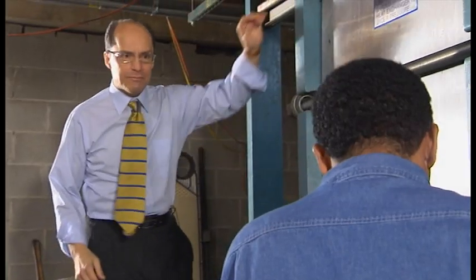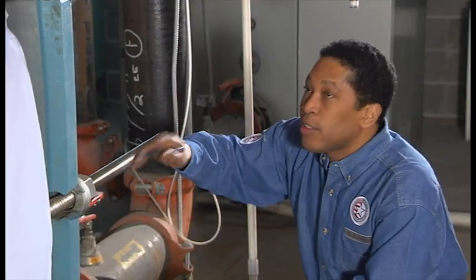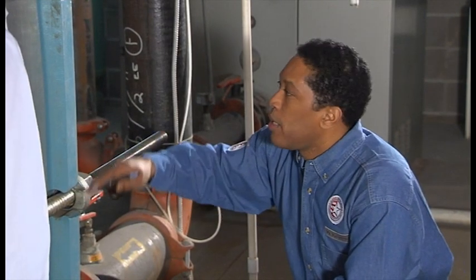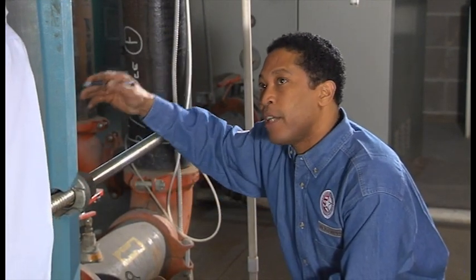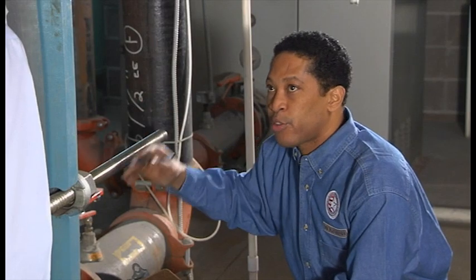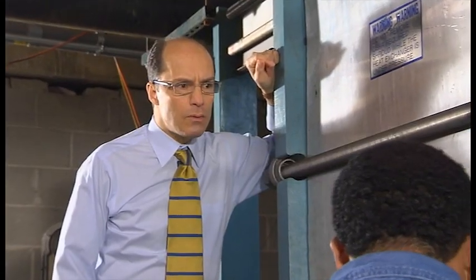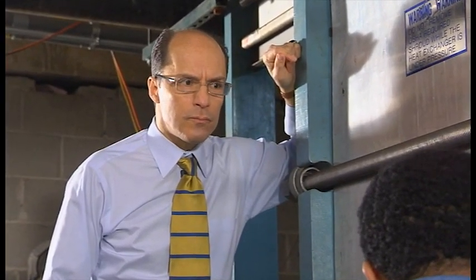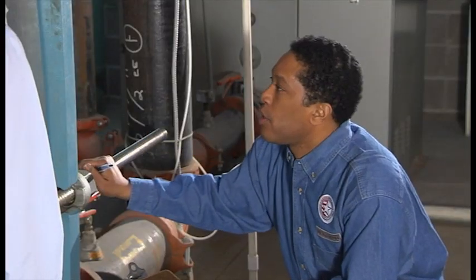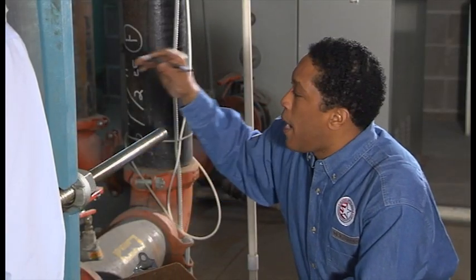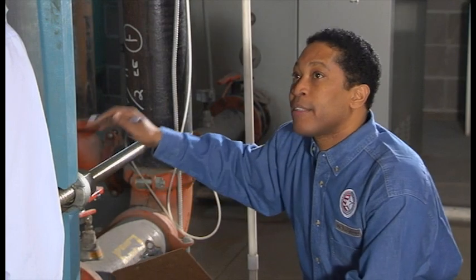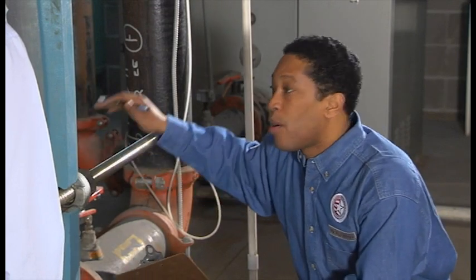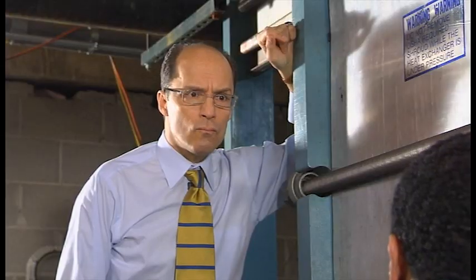Hey, how's it going? Well, I tested the water flow of the heat exchanger, and the cooling tower side of the heat exchanger is restricted, most likely with dirt that enters through the system during normal cooling tower operations and settles in the water. But what that means is that the system will not allow proper heat transfer.